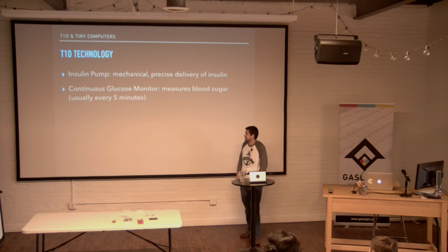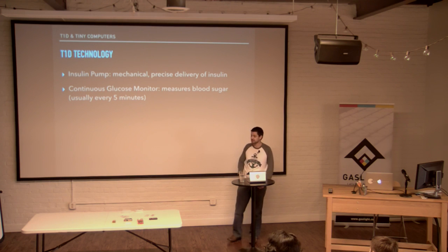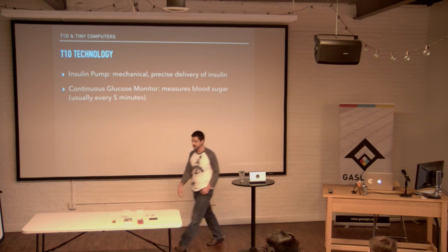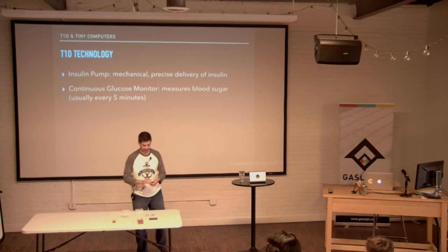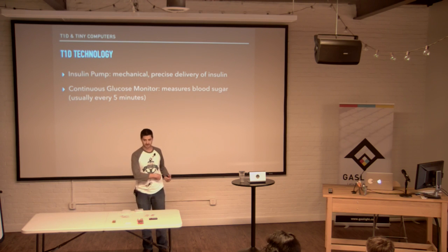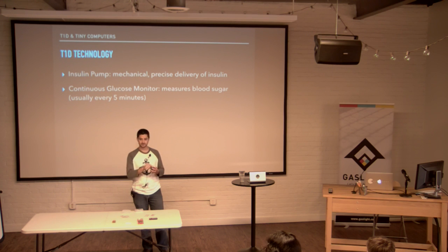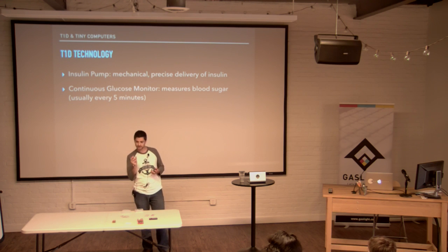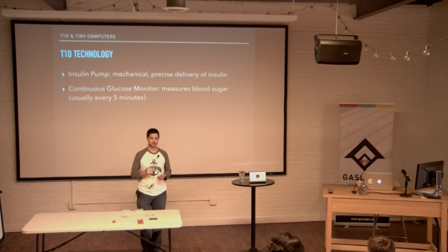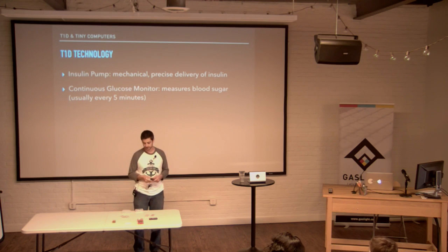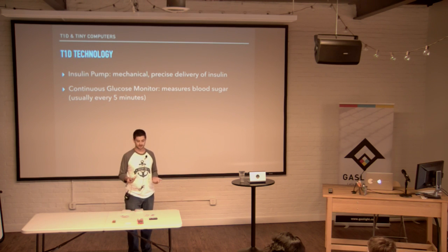The Type 1 diabetes technology that's out there right now — the state of the art on the market — has two main components. There's this thing called an insulin pump. If you can imagine this with a big tube attached, connected to your body, worn in your pocket — this is an insulin pump. It has a little reservoir of insulin and a small auger-type motor that very precisely pushes the right amount of insulin into your body. It can do both bolusing and basaling — constantly giving you a little bit of insulin, and when you tell it you're about to eat, it pushes a bit more.